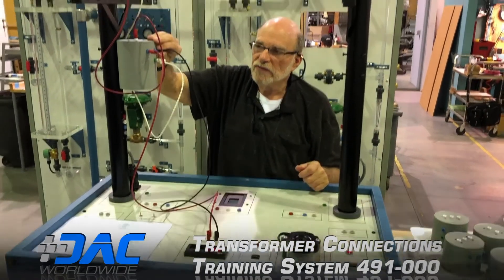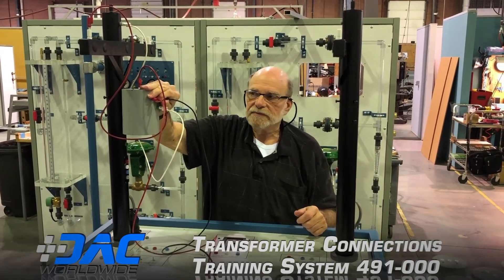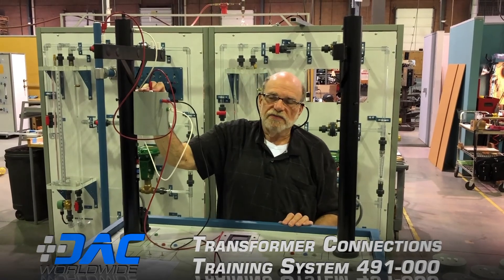You can see we're reading approximately 240 volts. If I move the meter connection to the center tap, we're reading about 120 volts. This is the type one single phase transformer.